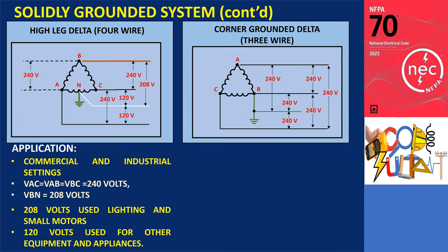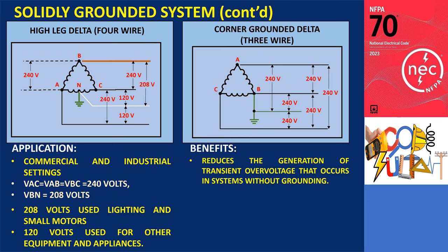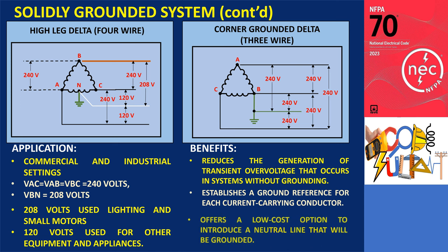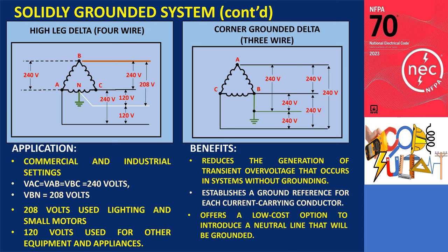Corner grounded delta is one of the earliest forms of grounded systems in electrical installations, offering a low-cost method of grounding a delta configuration. The grounding could be on any of the three phases from the transformer secondary, but the choice is usually the second or B phase for easy tracking. Benefits include reducing transient overvoltage, establishing a ground reference for each current-carrying conductor, and offering a low-cost option to introduce a grounded neutral line.